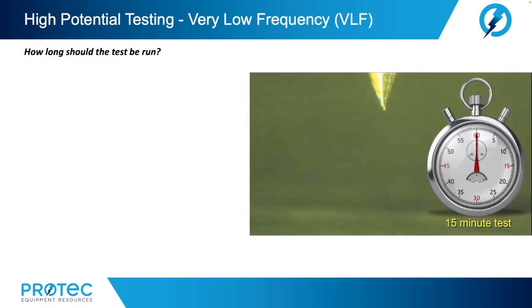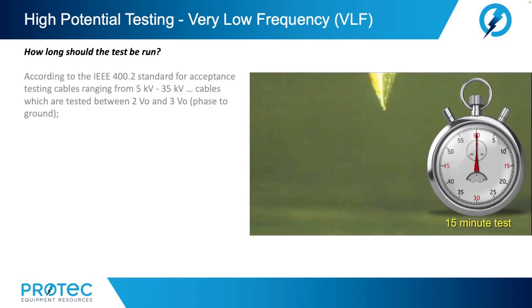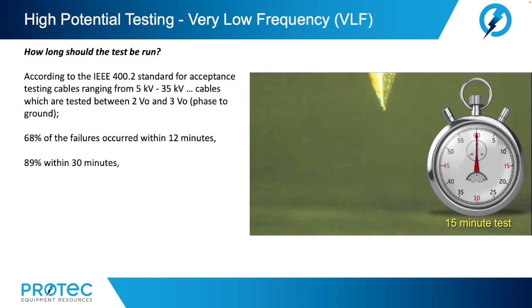Now, how long should a test be run? Well, according to IEEE 400.2, standard for acceptance testing cables ranging from 5 kV to 35 kV, cables which are tested between 2 times U-naught and 3 times U-naught phase to ground, 68% of failures occurred within 12 minutes of testing, 89% within 30 minutes, and 95% after 45 minutes, and 100% after 1 hour of applied test voltage.